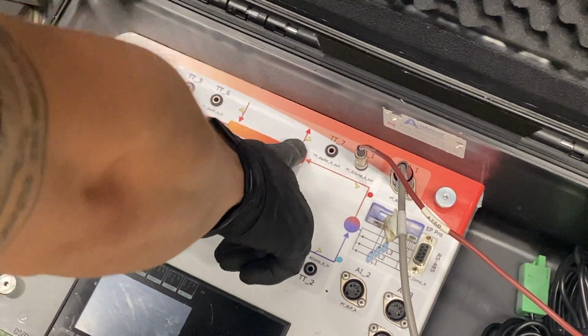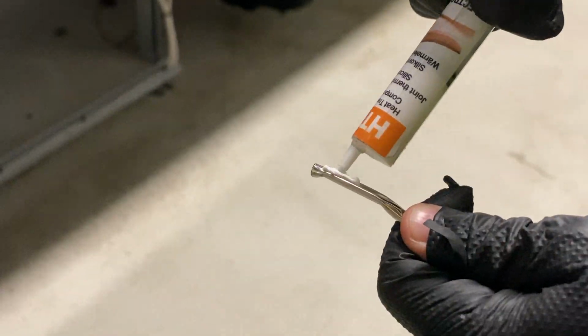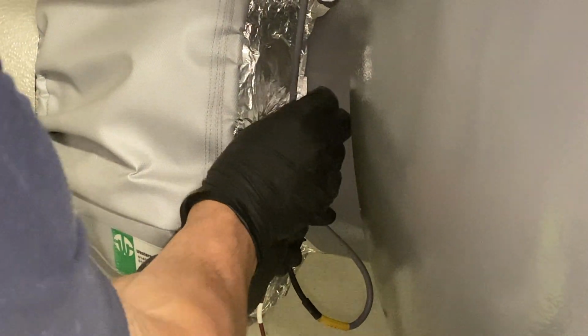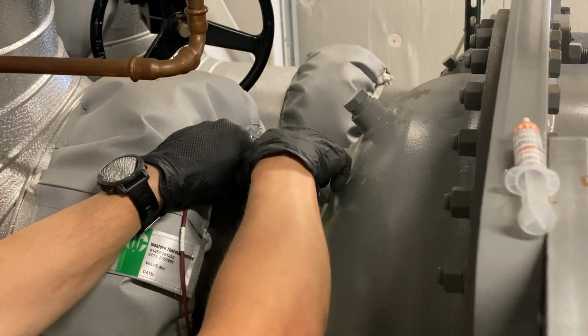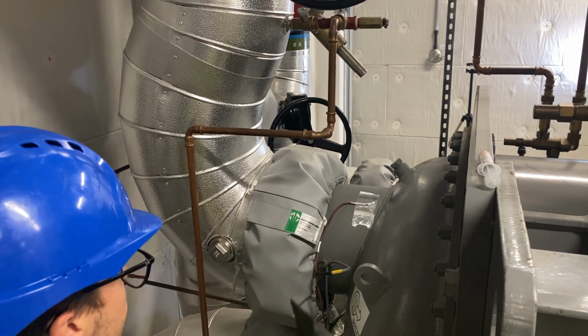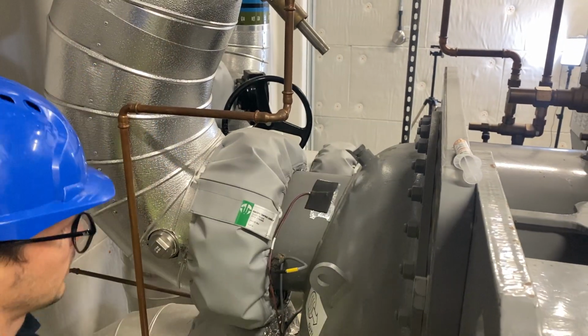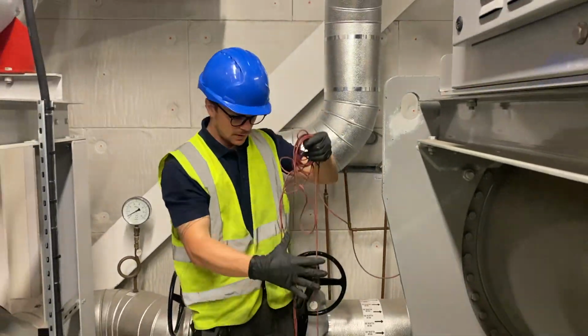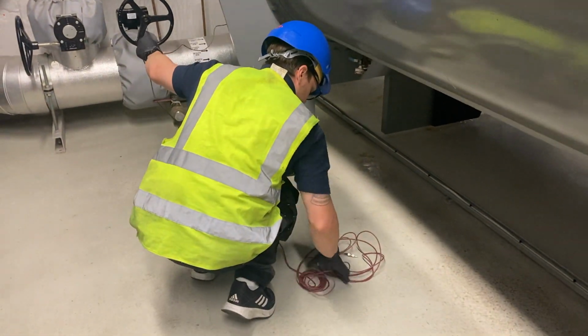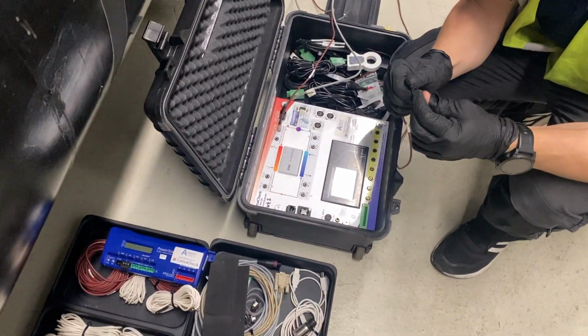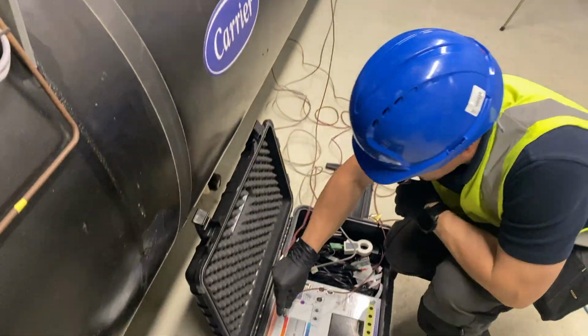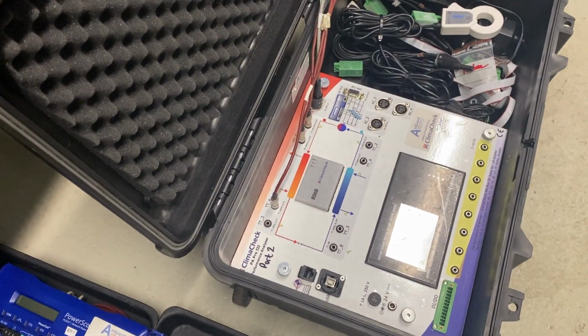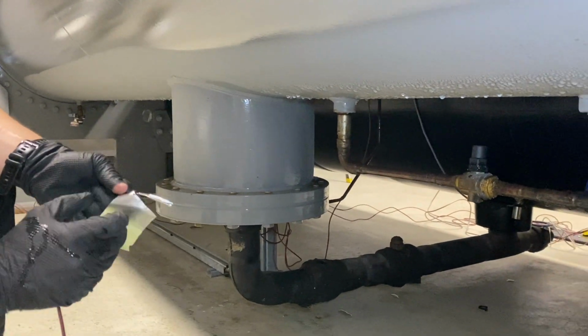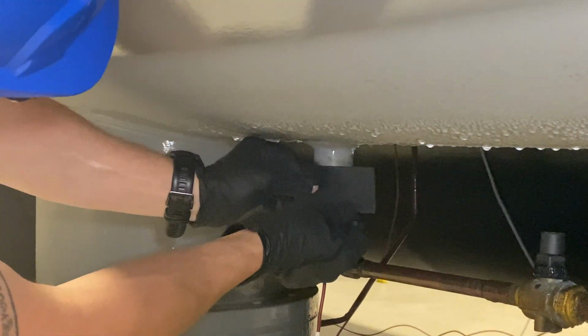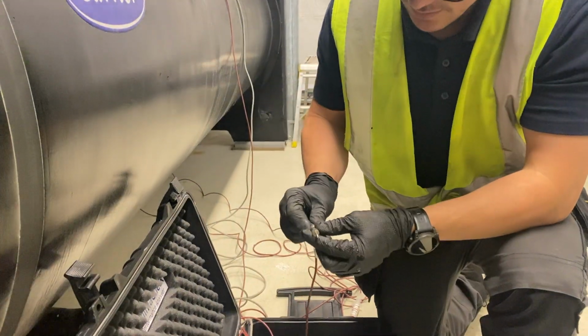Showing next two sensor wires, the temperature in and out of condenser water. Here we are fixing condenser in and out sensors to the condenser in and out pipe surfaces. The engineer is passing the sensor cables to the other side of the chiller, then plugging them in to the in and out sockets of the condenser water communication system. Here we are fitting a surface temperature sensor to the liquid line and plugging it in to the appropriate socket.